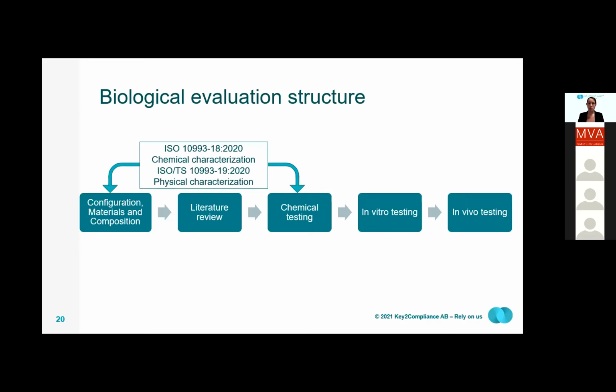And the very first step is the chemical testing. And after you have done the chemical testing, then you can proceed to perform biological testing, such as in vitro testing as a first step, or the last resort is to do animal testing. So as you see here, the chemical characterization is highly important, and that is described in part 18 of the ISO 10993 series. That comes in two steps, both this first step where you review the information you have at hand and in performing chemical testing.